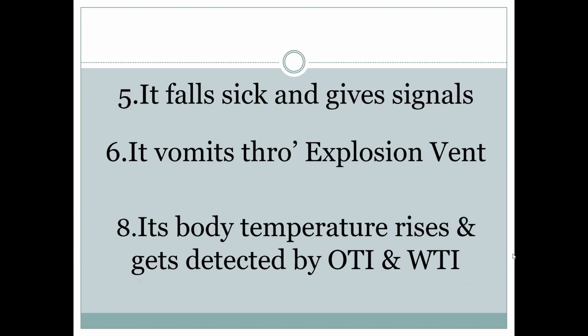Next. The transformer falls sick, and it gives a signal. There are so many attachments which indicate that the transformer is not working well. It is not healthy. There's some problem inside it. It vomits through the explosion vent, like the human body. When there is gas inside, the extra gas gets out through what is called the explosion vent, and there is an instrument attached to it so that the additional pressure gets equalized. So it starts working well. But if it is serious, then you have to attend to it. So it is like our human body.